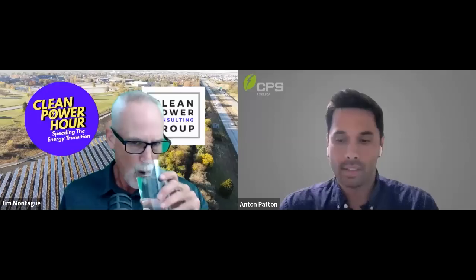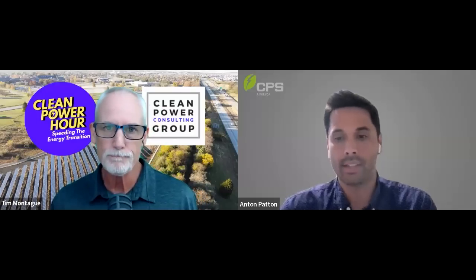Yeah, some of the things you mentioned, I think obviously the benefits on the operation side as you're looking at these systems that are going to be out in the field for 20 plus years. It's really not just the initial CapEx of the project that a lot of developers are looking at. A lot of the benefits are the lower risk of downtime if an inverter goes down. With a central, you've got maybe 5 or 6 megawatts in a single inverter, whereas if one string inverter goes down, it's a very small part of the system.